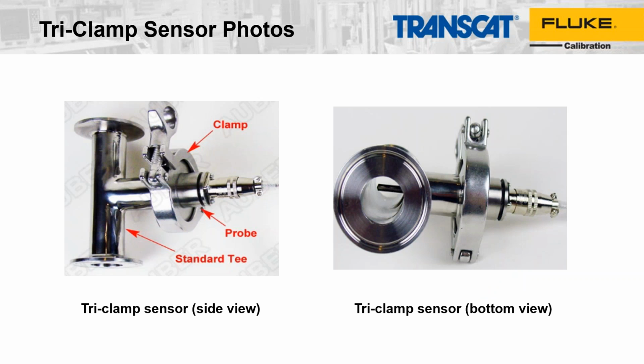So here are the pictures of the actual clamping system. You can see in the picture on the left, there's a clamp that goes around the flange, and the flange mates up with the piping system that's in the facility, and again makes it easy for someone to take the sensor out and calibrate it. And you can see on the right-hand picture where the temperature sensor now is inside, in this case, a T fitting that would be in the plumbing or the piping system, so that the temperature of the material going through there can be measured, and then that measurement sent off to either a PLC or a 4 to 20 milliamp control system in the facility.